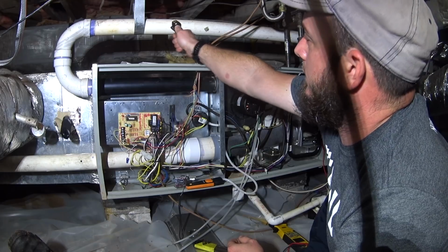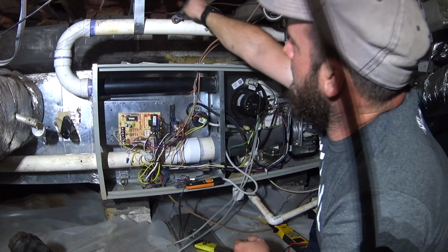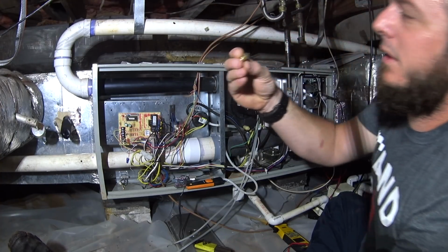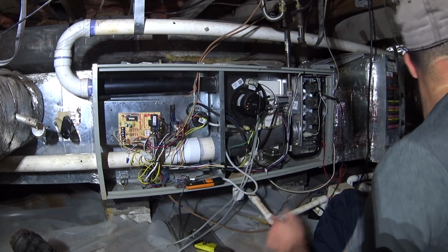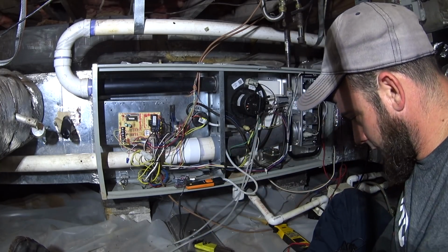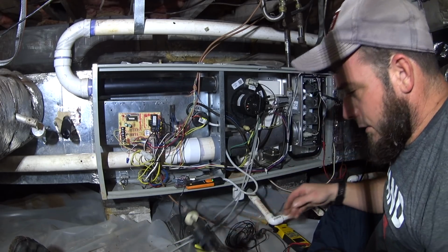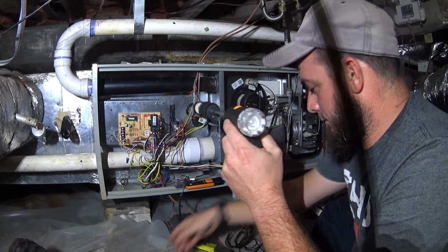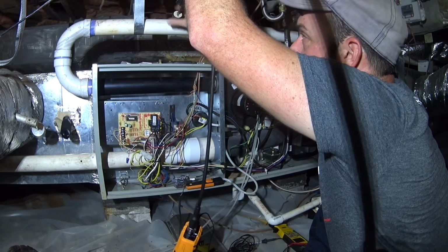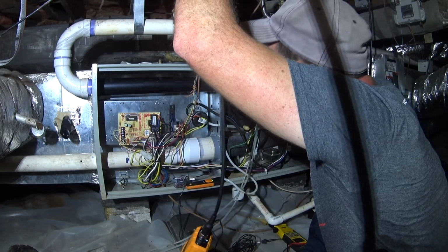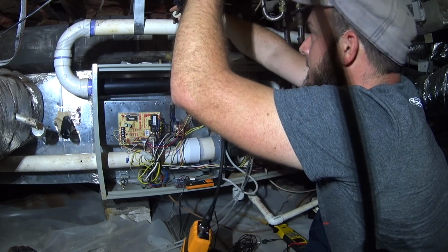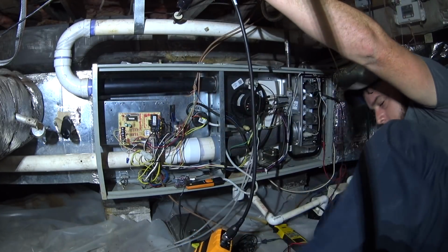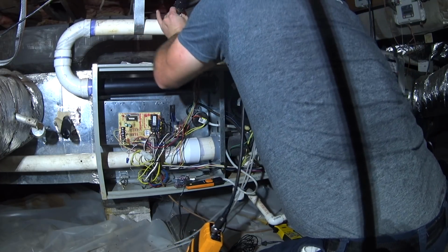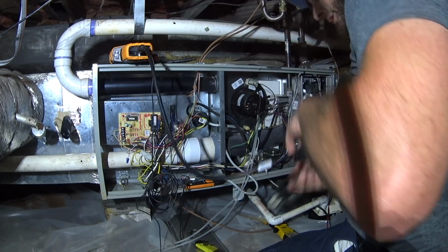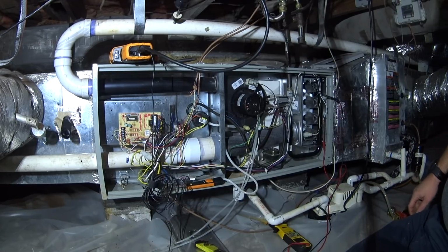We'll go ahead and get combustion set up before we go that far. I had a socket nut driver that would fit that plug, which is basically just an orifice with no hole in it, a burner orifice. So with the Testo 330i, there is no display. It is just like all the other displayless accessories available today, but it is basically just a Testo 330 rebuilt for Bluetooth communications. Let's see if I can get my adapter cone threaded in. It looks like I need to hold my mouth just right to do that again. Either that or this hole was for my old 320. But I think we should be able to get it to work. It looks like I'm going to have to open that hole up a little bit. Alright, we've got it in.